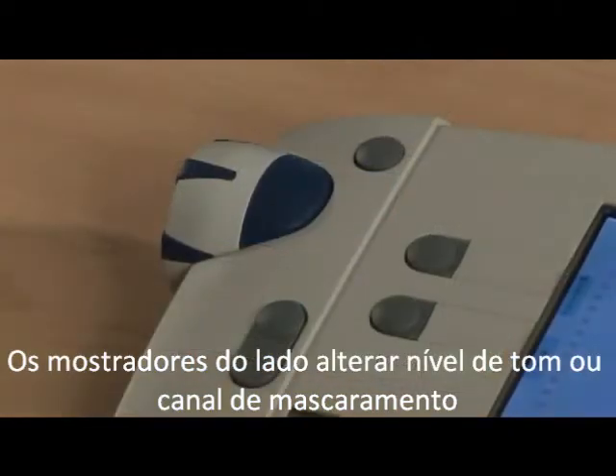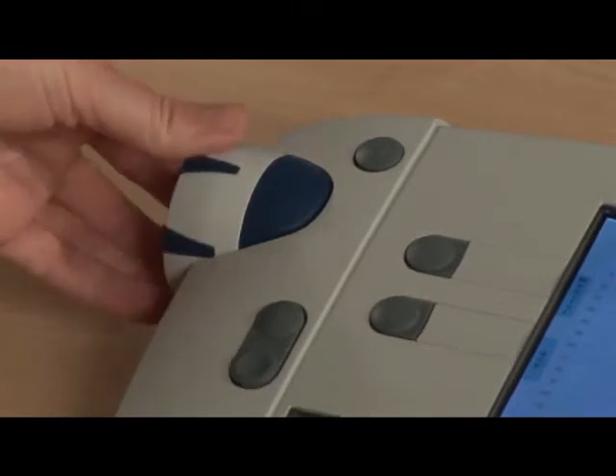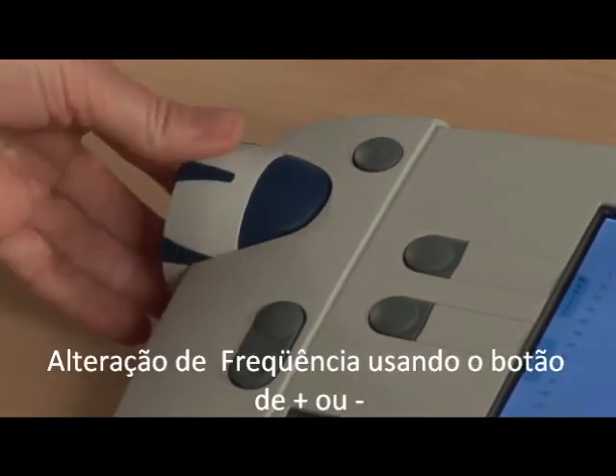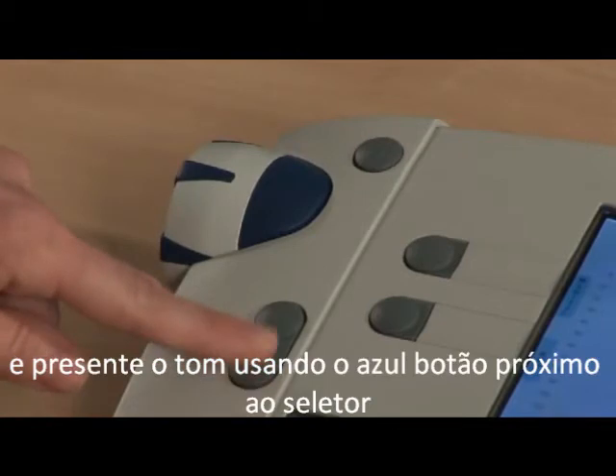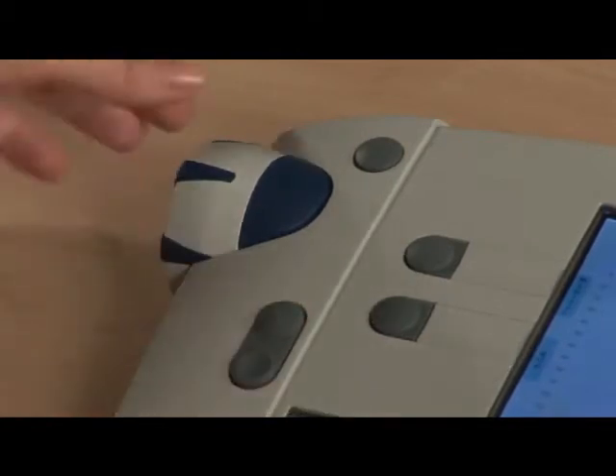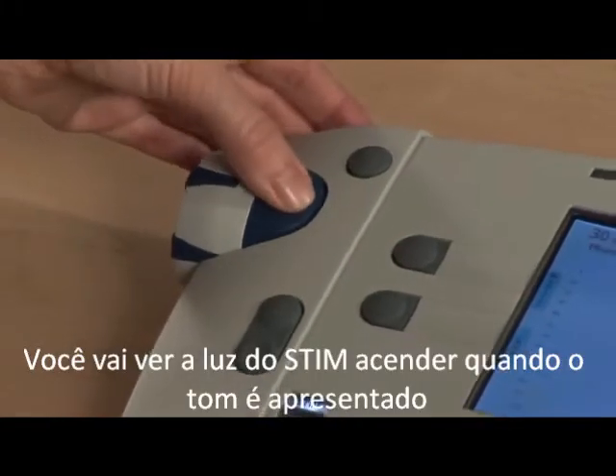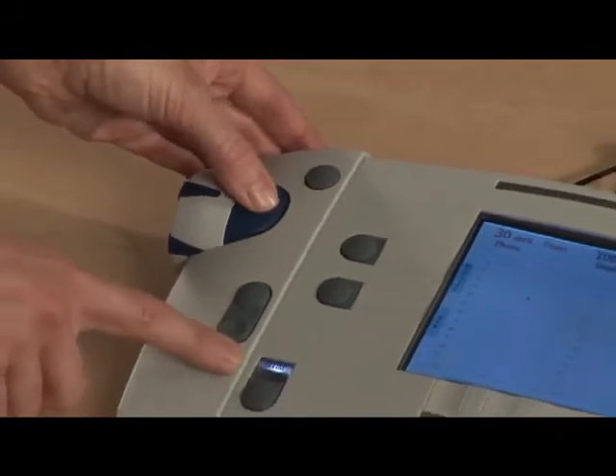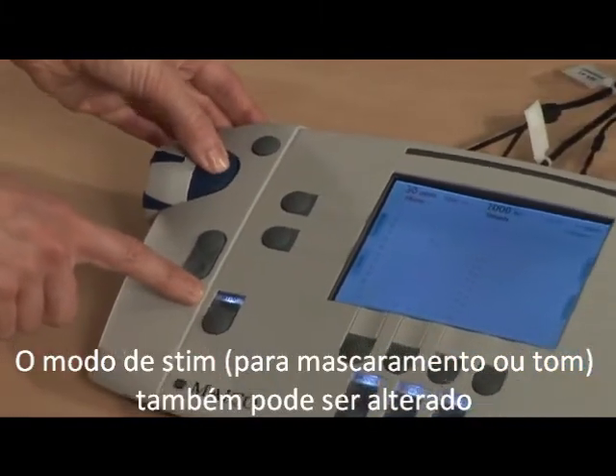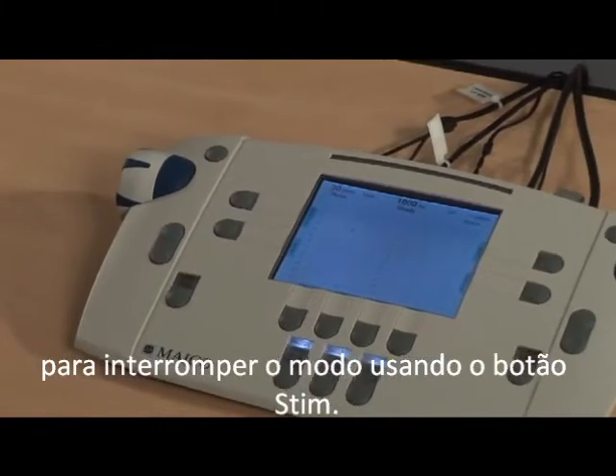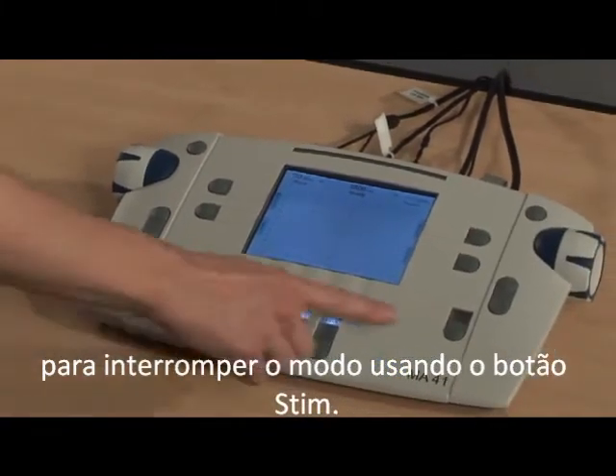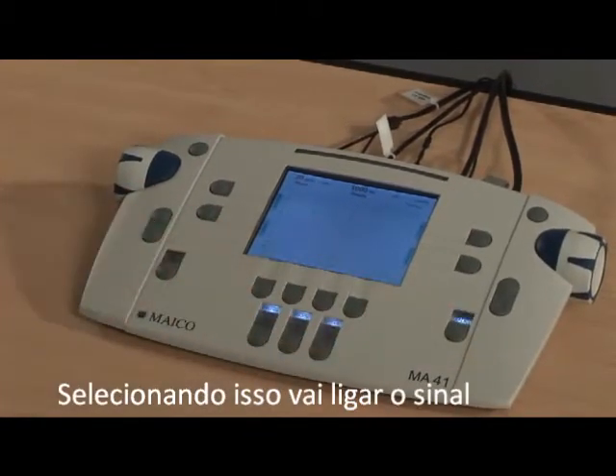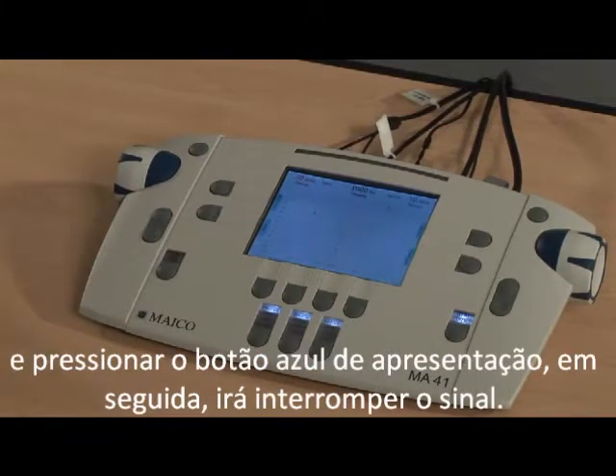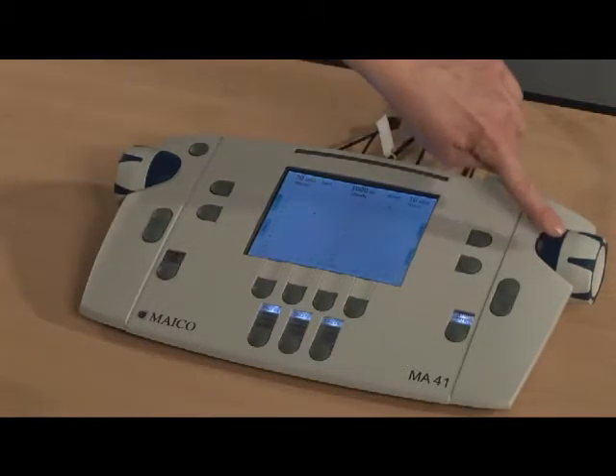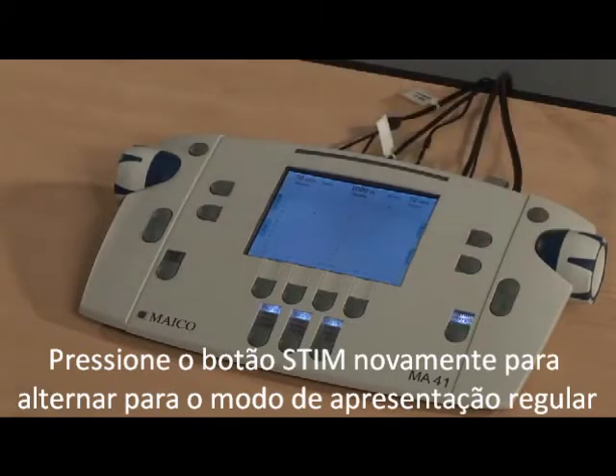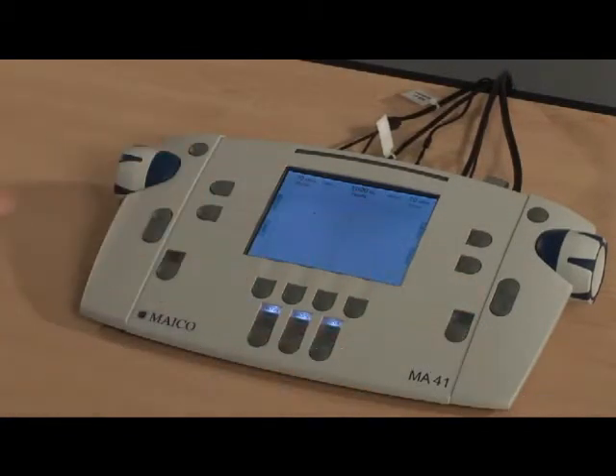The dials on the side change level for the tone or masking channel, change frequency using the plus or minus button, and present the tone using the blue button next to the dial. You will see the stim light flash when the tone is presented. The stim mode, for masking or the tone, can also be changed to interrupt mode using the stim button. Selecting this will turn the signal on, and pressing the blue presentation button will then interrupt the signal. Press the stim button again to toggle back to regular presentation mode.